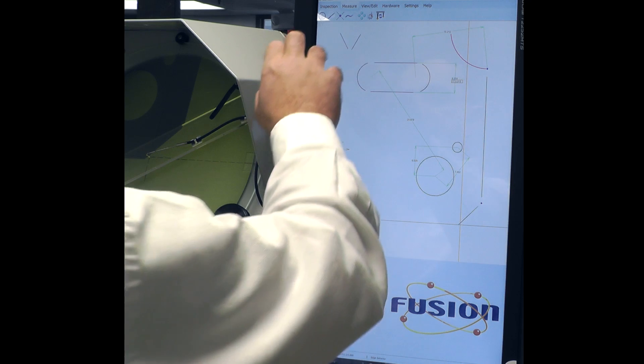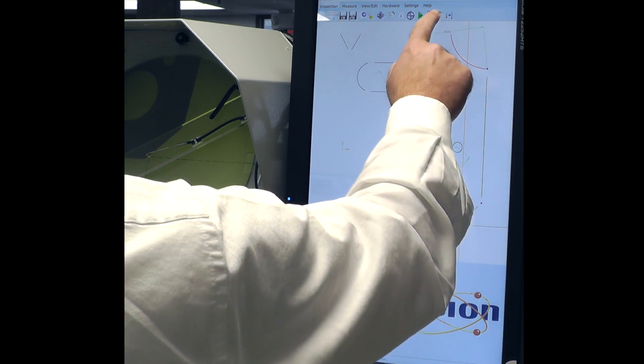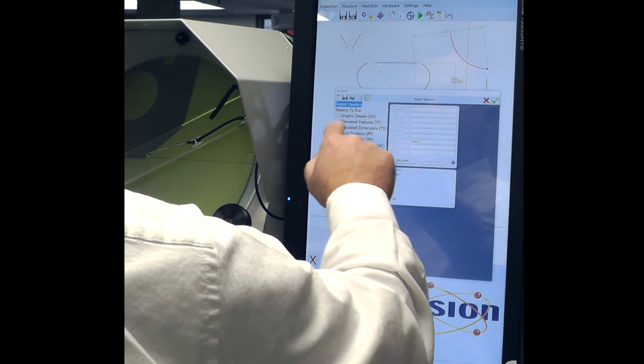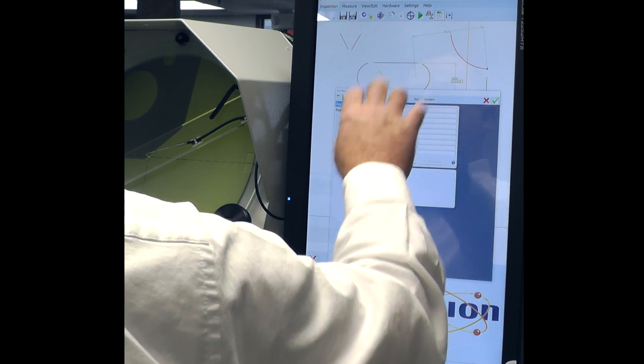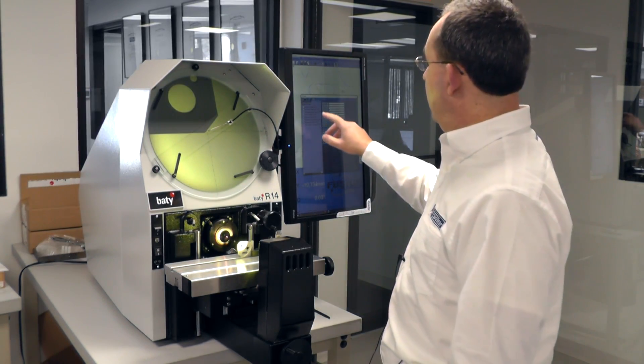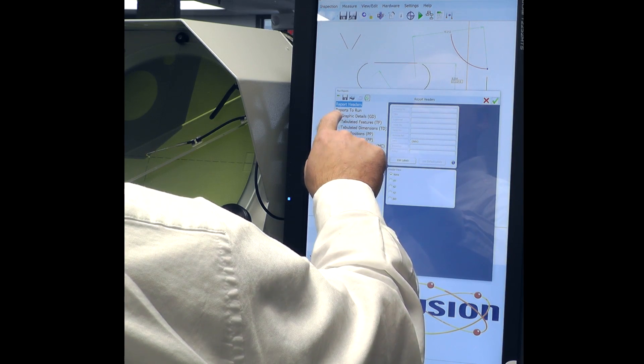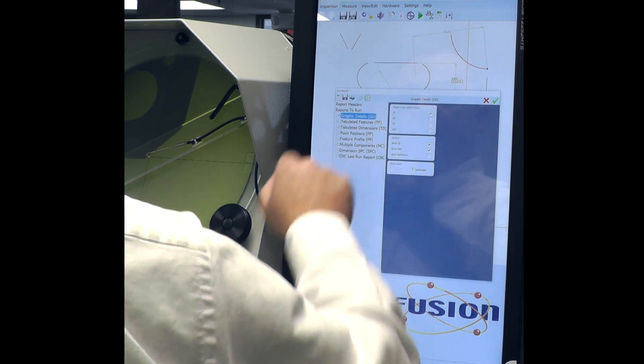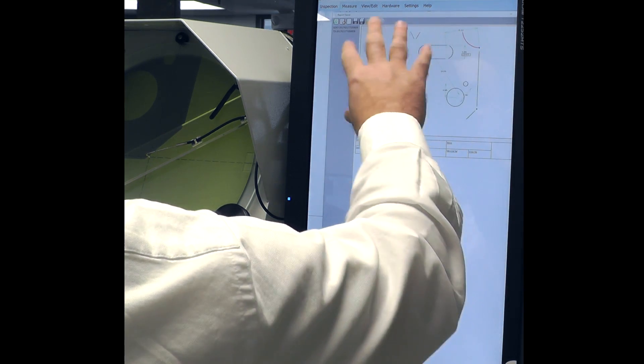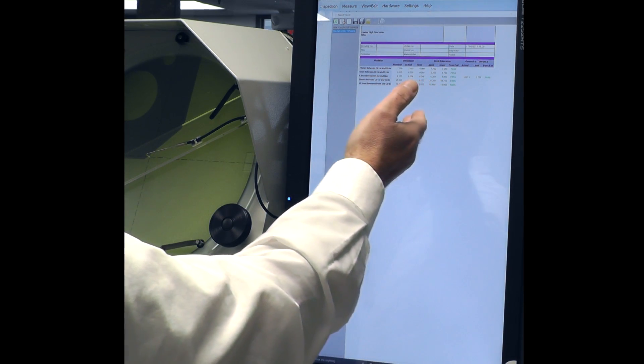I've done some more measurements here — let's see what our report looks like. Generate reports. In this case, we're going to run both a graphical report, which will give us this drawing dimensioned as we see it, and also tabulated dimensions, which is probably what the QC guy actually wants. And then we'll run it. Now we've got our dimensioned drawing up here, and if I select the second tab, I get my tabulated features with all the header data that you would want to put on for your QC department to stay compatible with ISO.